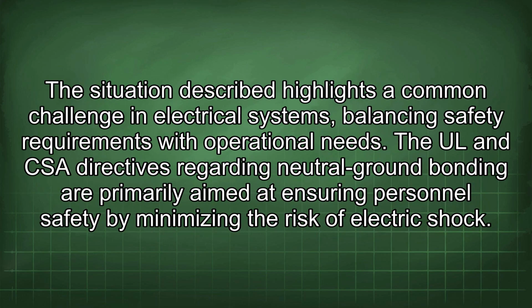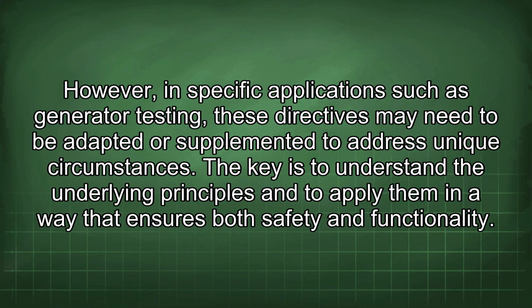The situation described highlights a common challenge in electrical systems, balancing safety requirements with operational needs. The UL and CSA directives regarding neutral ground bonding are primarily aimed at ensuring personnel safety by minimizing the risk of electric shock. However, in specific applications such as generator testing, these directives may need to be adapted or supplemented to address unique circumstances. The key is to understand the underlying principles and to apply them in a way that ensures both safety and functionality.